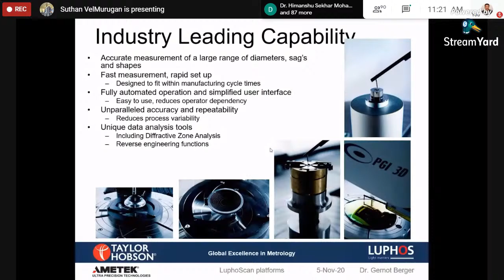Again, accuracy-wise, the capability of the machine is that we can measure up to a 300 millimeter diameter. It's a bigger diameter part. The sag, in the sense of depth, we can measure up to 50 millimeter depth. It could be concave or convex. Either profile can be measured. The spatial frequency is 125 nanometers. As I said some few minutes back, it can collect 8,000 points per millimeter. The calculation is from here. It picks up every 0.125 microns, or every 125 nanometers, 1 point in the x-axis. So in a millimeter, roughly about 8,000 points. And the repeatability, or the accuracy, we can say, is less than 50 nanometers.